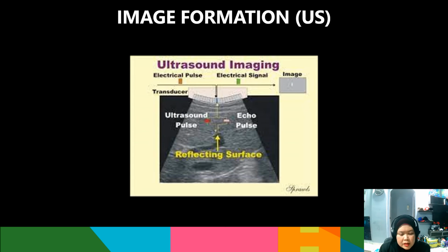For the ultrasound, ultrasonic image formation is created using a pulse echo method of ultrasound production and detection. Each pulse is transmitted directionally into the patient and then experiences partial reflection from tissue interfaces that create echoes, which return to the transducer. Image formation using the pulse echo approach requires a few hardware components such as the beamformer, pulser, receiver, amplifier, scan converter, image memory, and display system.